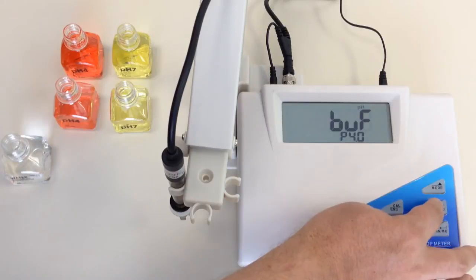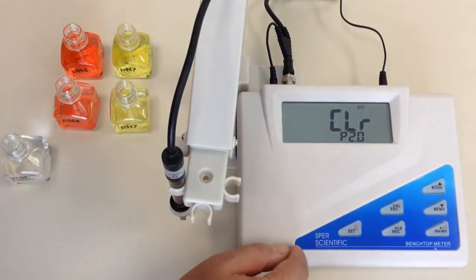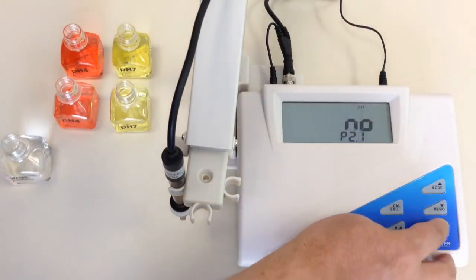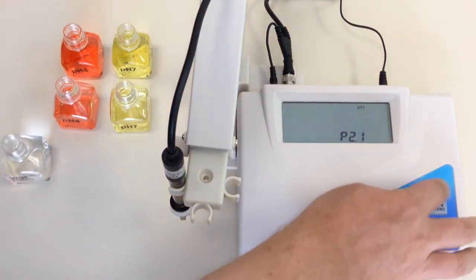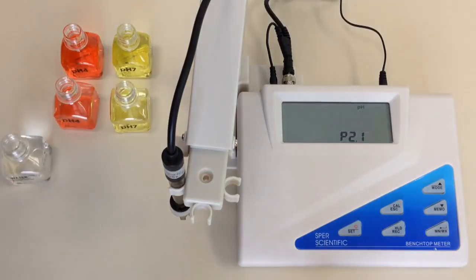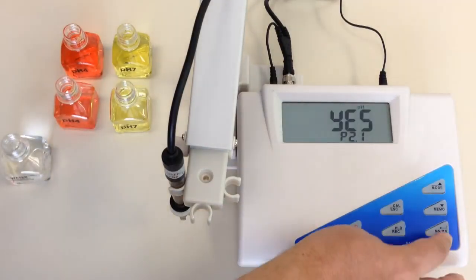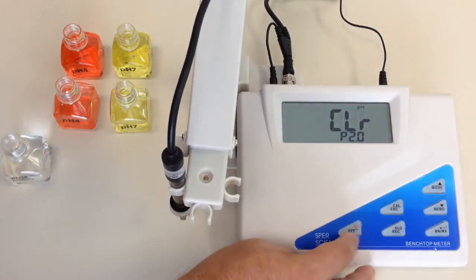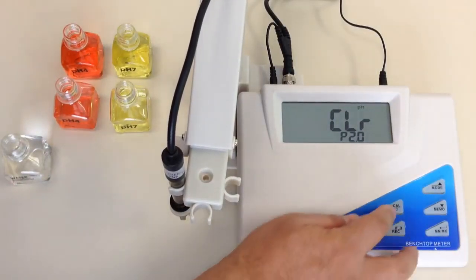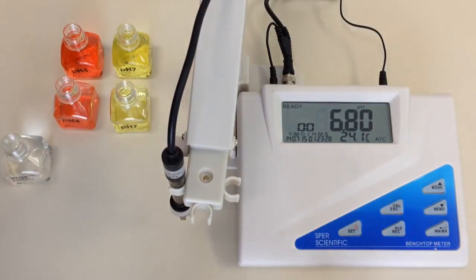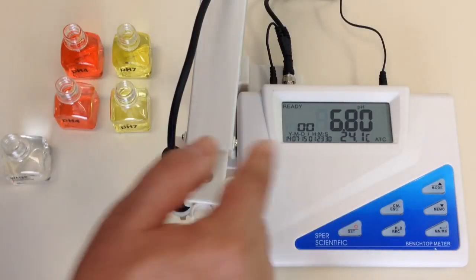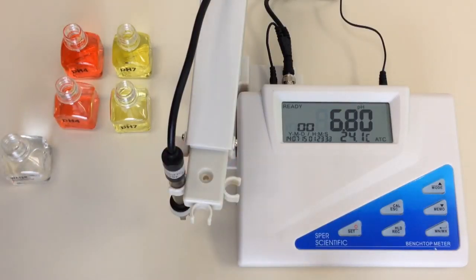Now, if I did receive the error 13 message, the first thing I'd have to do is go to P2, hit the min-max, tell it to go to yes. Now this is going to reset all my factory settings, and so if there's anything that's being stored on the particular meter, please note those are going to be all wiped out. So in this case, I'm going to go ahead and hit yes. Now just to make sure that the unit is cleared, I'm going to hit escape and go back to the very beginning. If you had a P13 message, you should go back to a normal screen such as this.